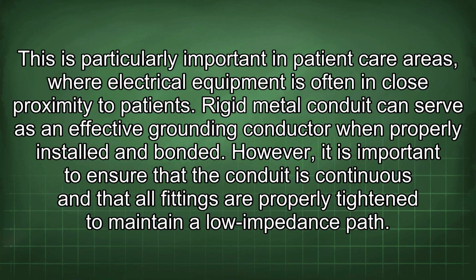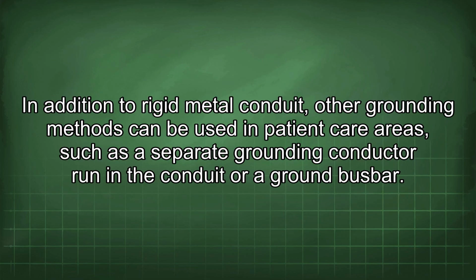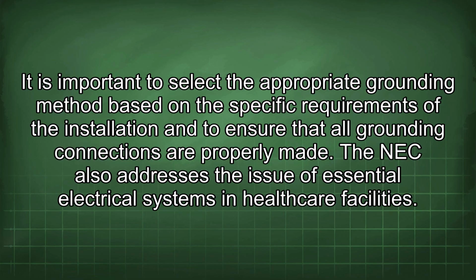a low impedance path. In addition to rigid metal conduit, other grounding methods can be used in patient care areas, such as a separate grounding conductor run in the conduit or a ground busbar. It is important to select the appropriate grounding method based on the specific requirements of the installation and to ensure that all grounding connections are properly made. The NEC also addresses the issue of essential electrical systems in healthcare facilities.